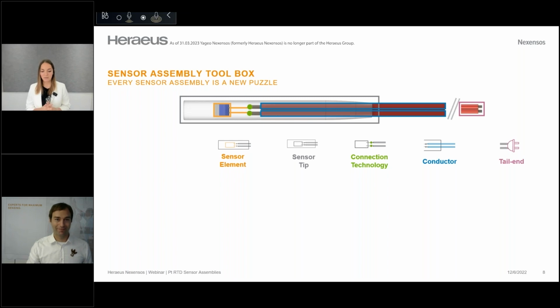Then we can see the different components of that EC3032, and that's also the setup of all other sensor assemblies. So a sensor assembly consists first of all of what we can see here in orange, a sensor element. Then we can see in gray a sensor tip, which could be a sensor housing and also a protection material. Then we have the connection technology, here shown in green, which is really the connection from the sensor lead wire to the cable. And then we can see in blue the conductor, and in purple the tail end.